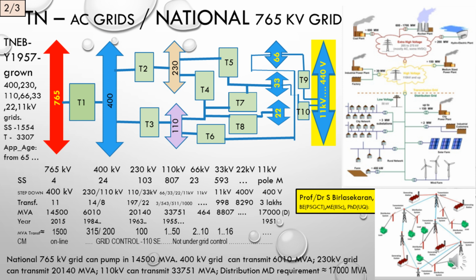The second slide shows the Tamil Nadu high voltage AC grids and the national 765 kV grid. As all of us know, Tamil Nadu EB was formed only in 1957 and it has grown, as shown at the top, into 400, 230, 110, 66, 33, 22, 11 kV grids to receive the energy and distribute it to the consumers. The number of main substations is running to 1554, and the transformers mainly used are something like 3307, and the age of the transformers starts from something installed around 1965.